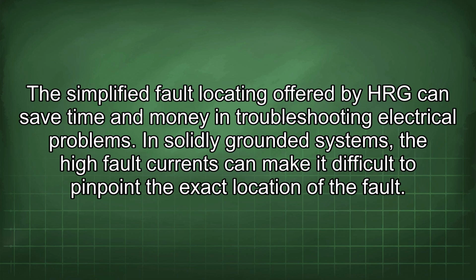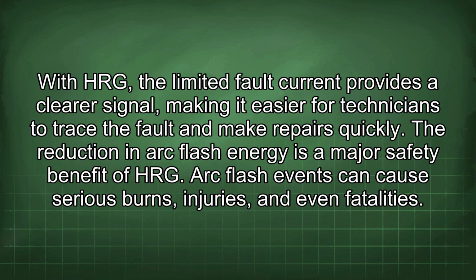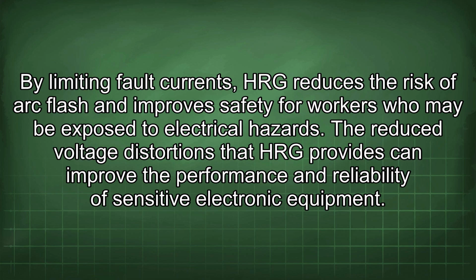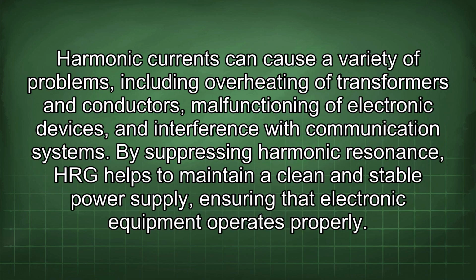In solidly grounded systems, the high fault currents can make it difficult to pinpoint the exact location of the fault. With HRG, the limited fault current provides a clearer signal, making it easier for technicians to trace the fault and make repairs quickly. The reduction in arc flash energy is a major safety benefit of HRG. Arc flash events can cause serious burns, injuries, and even fatalities. By limiting fault currents, HRG reduces the risk of arc flash and improves safety for workers who may be exposed to electrical hazards. The reduced voltage distortions that HRG provides can improve the performance and reliability of sensitive electronic equipment. Harmonic currents can cause a variety of problems, including overheating of transformers and conductors, malfunctioning of electronic devices, and interference with communication systems.